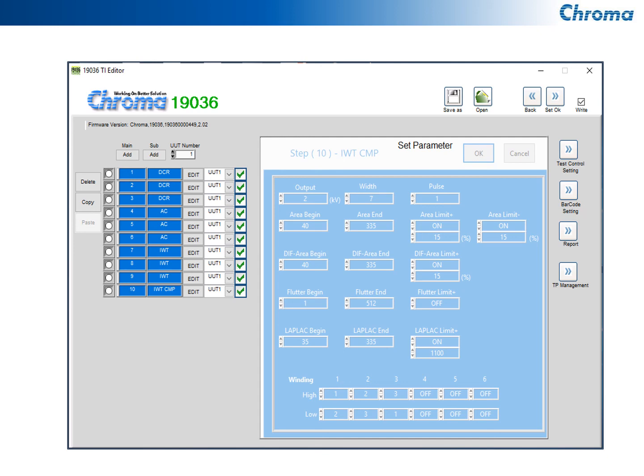Also, other little sidelight into this is that you can also use like a barcode reader to, if your devices have some type of barcoding and labeling, you can then use that to make sure that you have the proper test program prior to running the test for your device, and also to capture the device's serial number or indicate the model number of the unit during test.